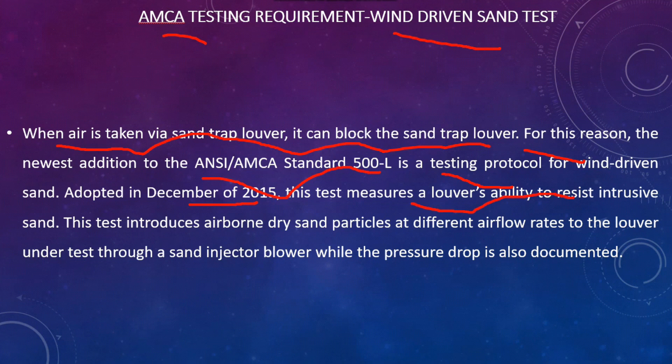This test introduces dry sand particles at different airflow rates to the louver through a sand injector blower, while the pressure drop is also documented. In one test, we can measure the pressure drop value. At different flow rates, sand will be thrown over the louver with the help of a fan, and at this point we can monitor the pressure drop as well as the sand rejection performance.